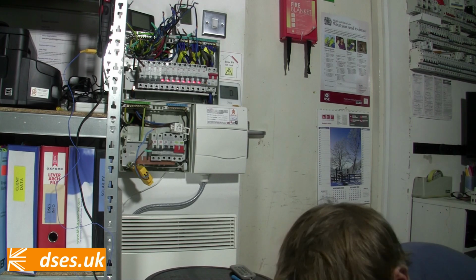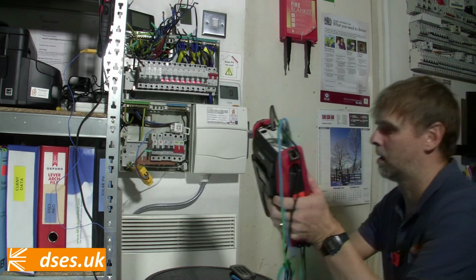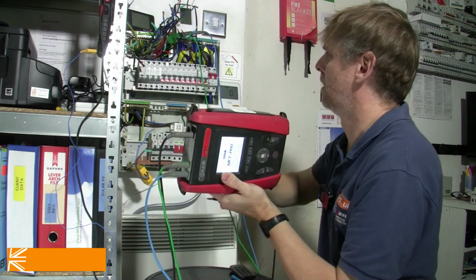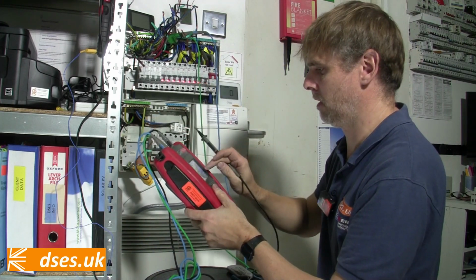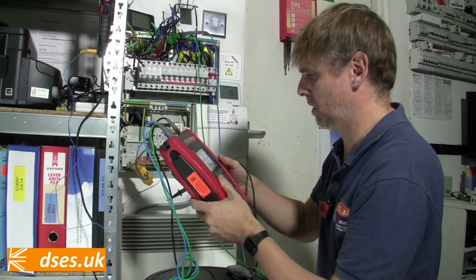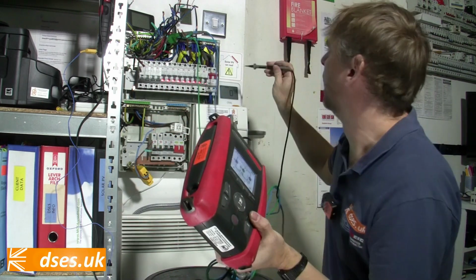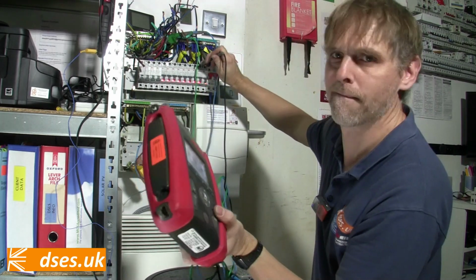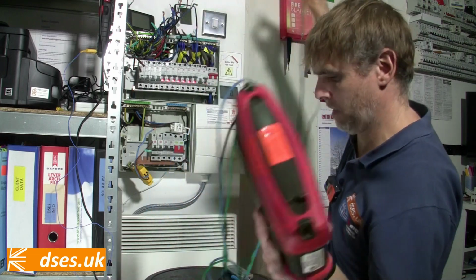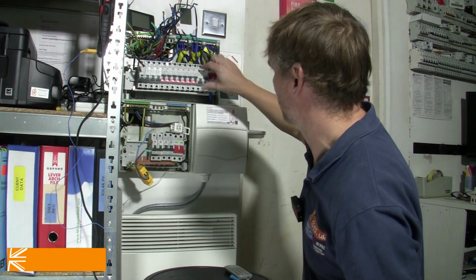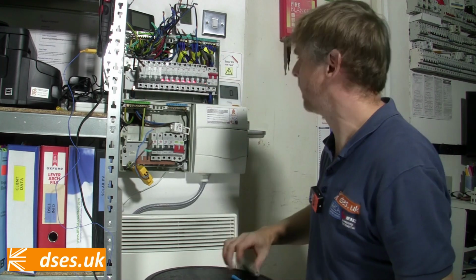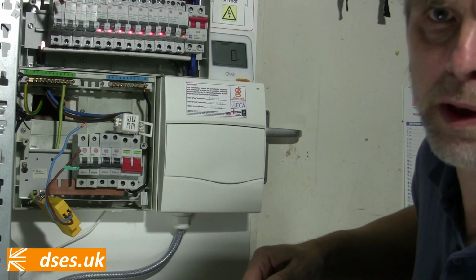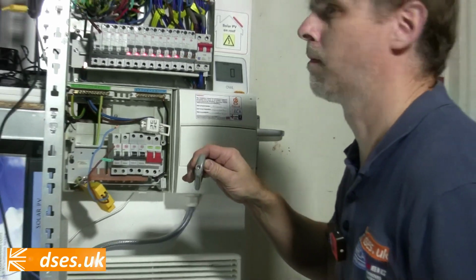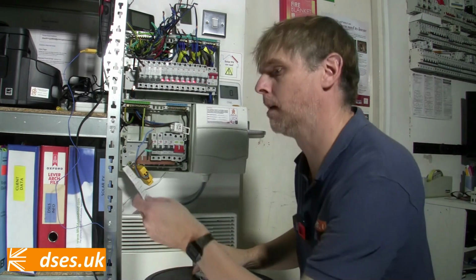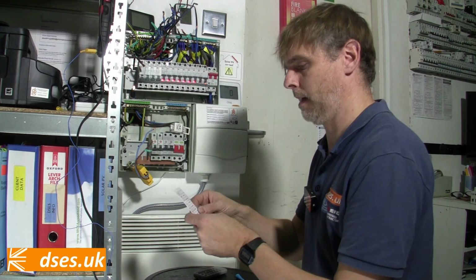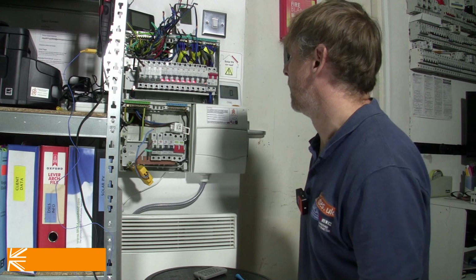Let's compare that then to an earth leakage trip. Stick that on earth. And we'll do the neighbouring device, shall we, just for comparison. So I'm going to set this to RCD, type A, 1 times. Let's stick that on load on circuit 2. Lovely stuff, 78 millisecond trip time, which is well within the 1 time specification, of course. And look at that, we have 3 pulses on that second device, indicating it's tripped off because of an earth leakage fault. 2 pulses, I believe, just consult the sticker, 2 pulses would be an over voltage error, and a yellow and red flashing would be a failed self-test. So that's all rather spiffing actually, isn't it?